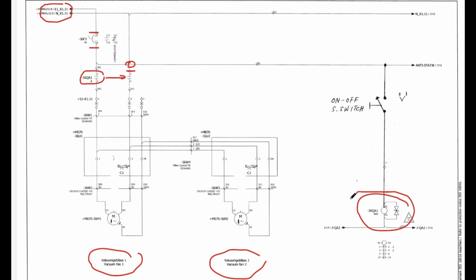It means this contactor is off. When we come here, we see A1 and A2 are the coil terminals, the supply terminals. Here we see the on off switch. Suppose the on off switch is at the off position, the 0 position, that's why it's not getting on. But maybe the switch is at 1, meaning the contact circuit is closed, but the contact is defective. So the same black probe stays here, we connect the positive probe here, and supply voltage is 110. But when we connect here, oh, supply is missing, which means our selector switch normally open contact is defective. I showed you the contact already, so we will just change that contact and our problem should be solved.